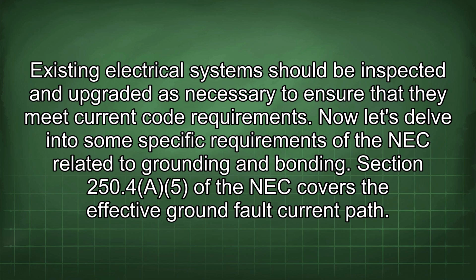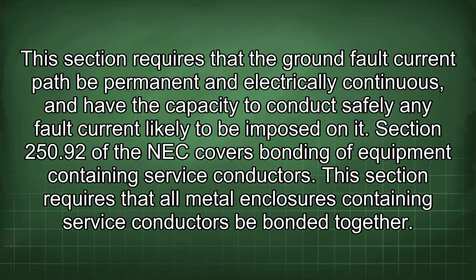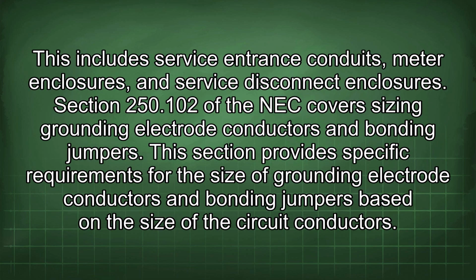Now let's delve into some specific requirements of the NEC related to grounding and bonding. Section 250.4 of the NEC covers the effective ground fault current path. This section requires that the ground fault current path be permanent and electrically continuous, and have the capacity to conduct safely any fault current likely to be imposed on it. Section 250.92 of the NEC covers bonding of equipment containing service conductors. This section requires that all metal enclosures containing service conductors be bonded together. This includes service entrance conduits, meter enclosures, and service disconnect enclosures.